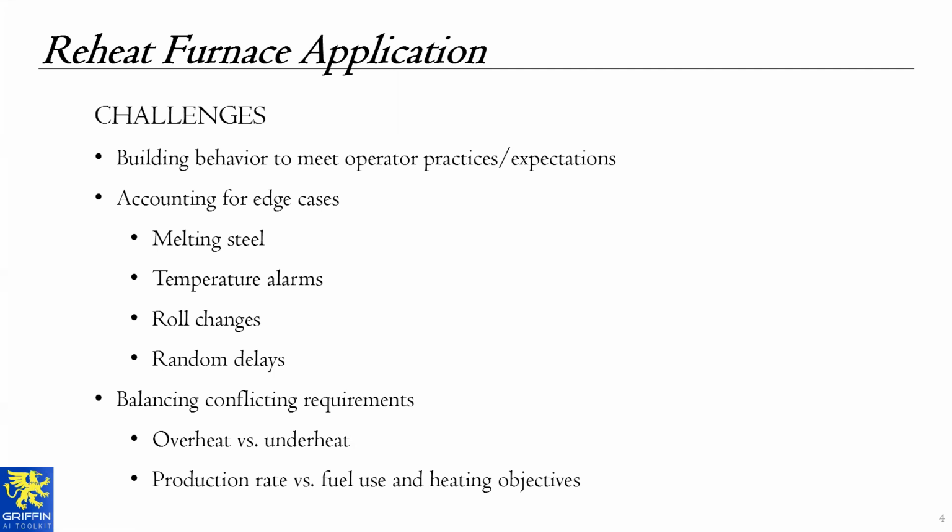You probably have to cool things down so you don't overheat the steel. And if a delay is going to be really long, you might even consider backing temperatures off to save fuel, of course, with the caveat that you don't want them to have to wait when they do come back online. So handling all of that, I handle all of those cases a little differently within the application.